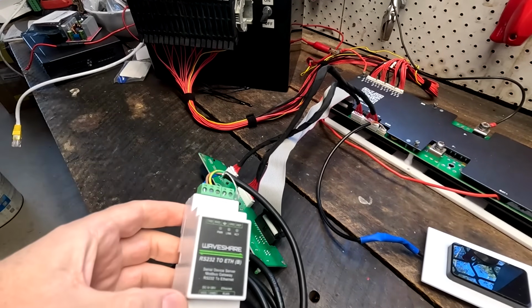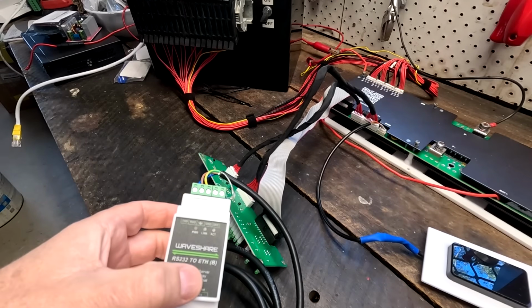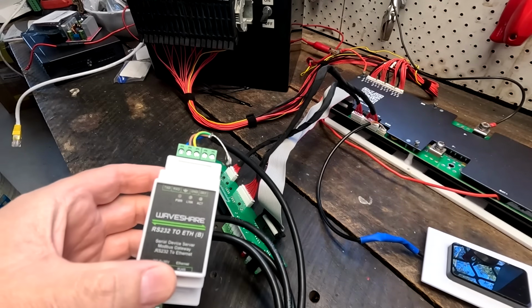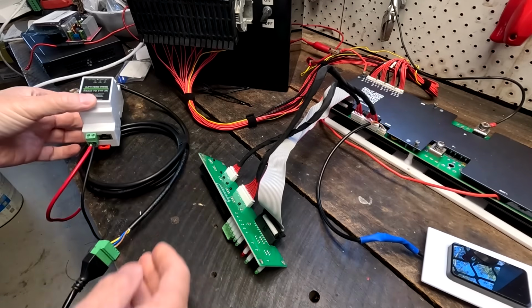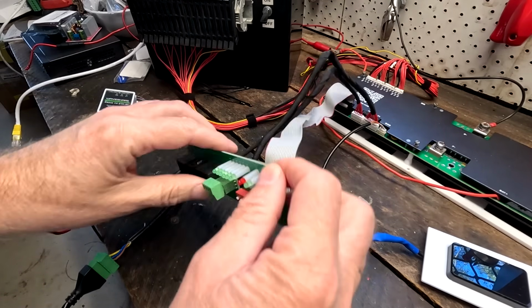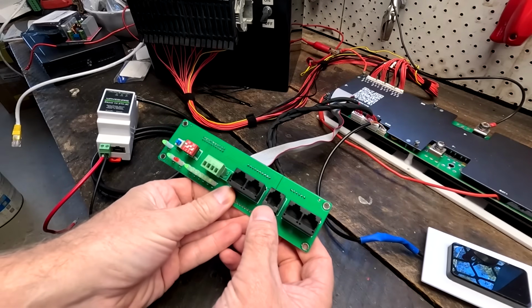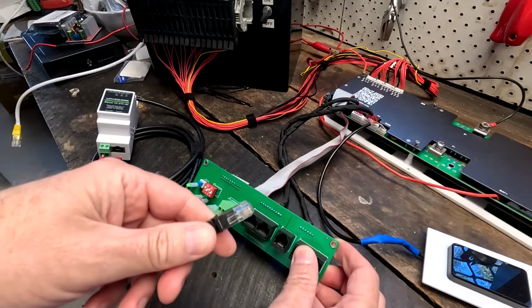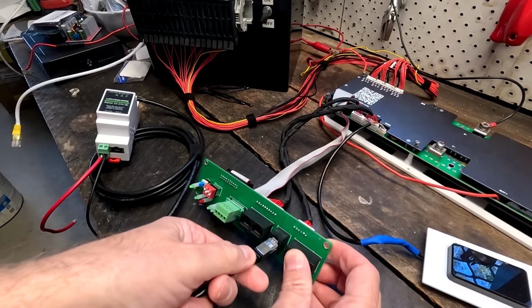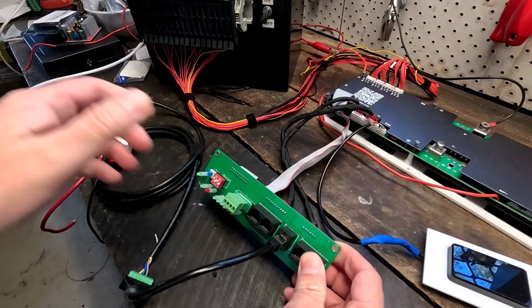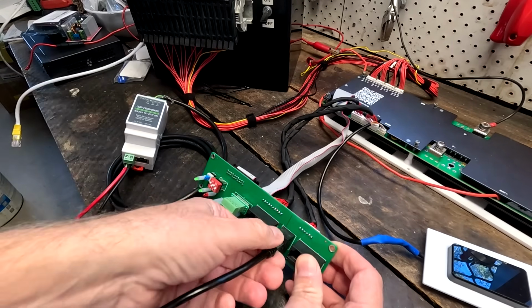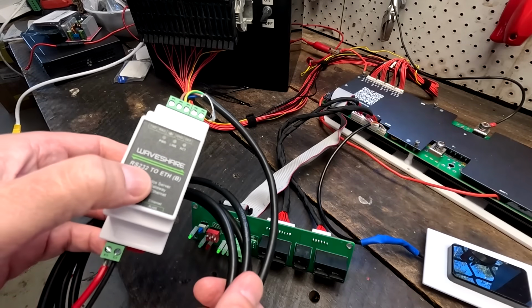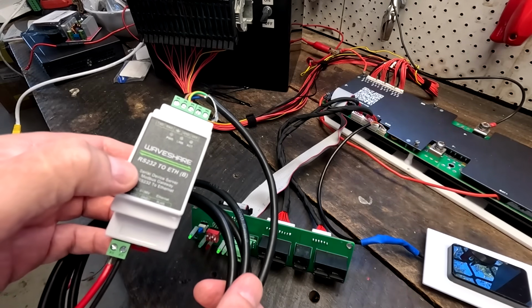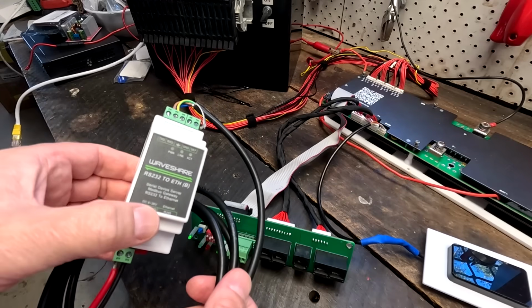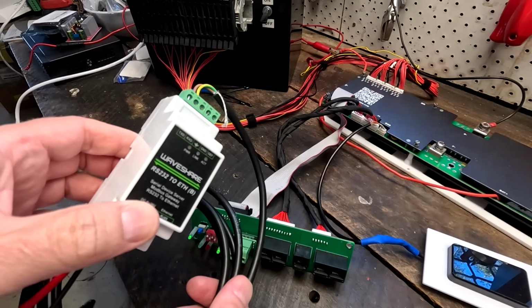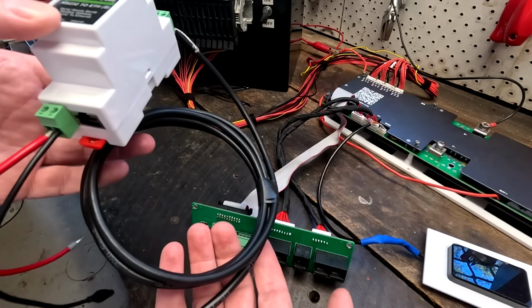Unfortunately, we cannot use the Waveshare RS232 to Ethernet server or gateway anymore, because the RS232 protocol of the JK inverter BMS does not match the protocol of the PACE BMS. So even if I plug this in here, it will not work. So we have to replace the RS232 to Ethernet gateway with an RS485 to Ethernet gateway. It's just a different device, but apart from that, the exact same process.